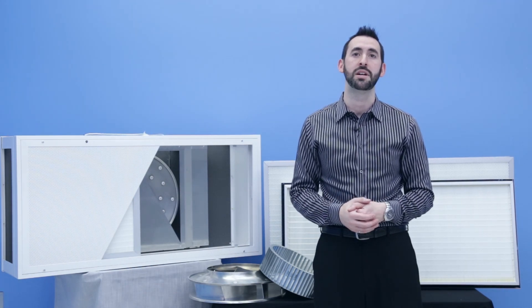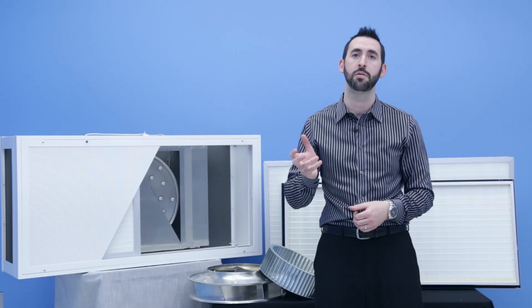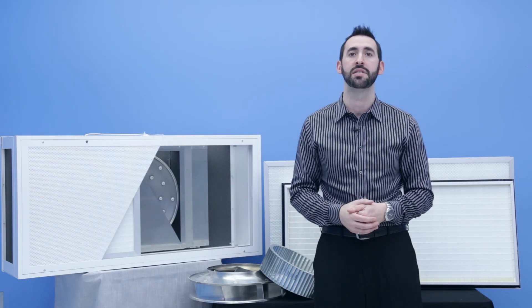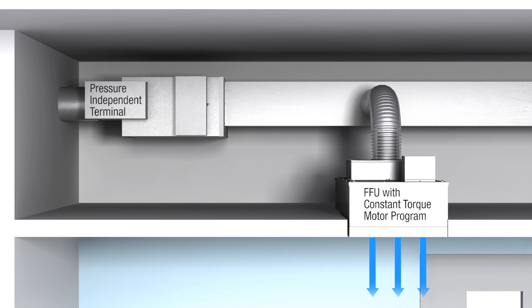The second motor program is constant torque. The constant torque motor program maintains the torque or the rotational force of the motor independent of the static pressure as the filter loads. To maintain constant airflow through the fan filter unit with a constant torque program, an upstream pressure independent terminal or Venturi valve is required.